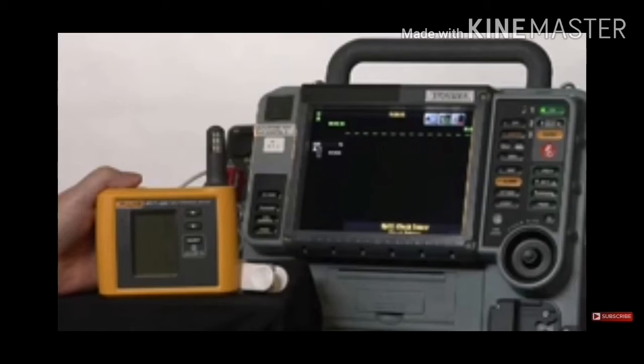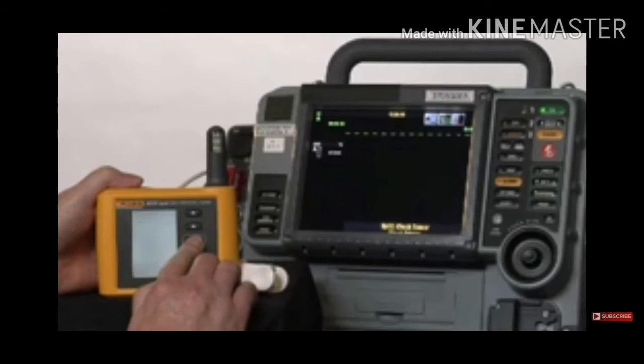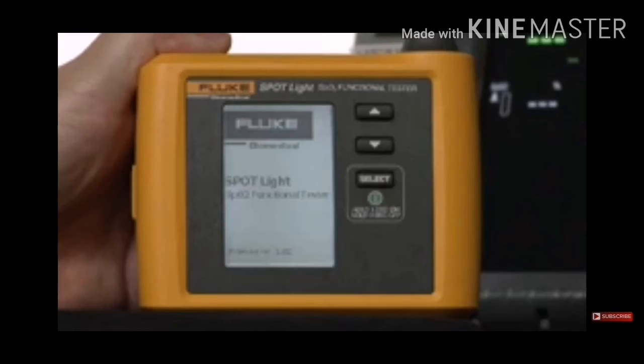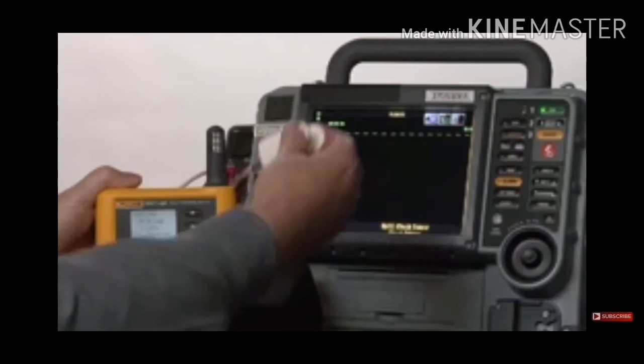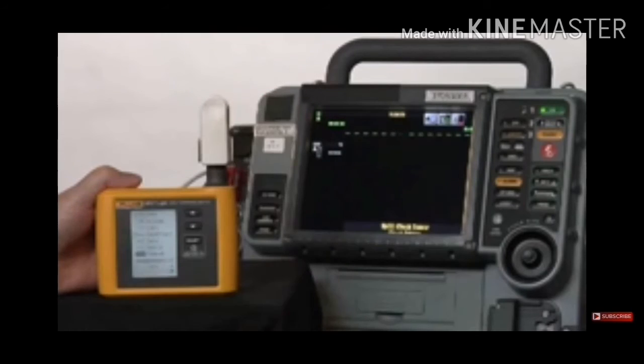In this case, we find the device turned on. It's a defibrillator. And we will turn on our Spotlight SpO2 functional tester. Wait for it to go through its self-check. And we will then connect the oximeter sensor from the medical device, and we'll watch this bar down at the bottom. It's called the signal strength bar, and you can see that it has a good signal, and you will begin to see the display on the screen of the defibrillator.